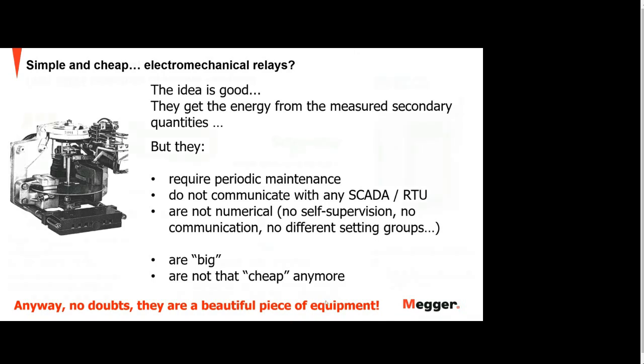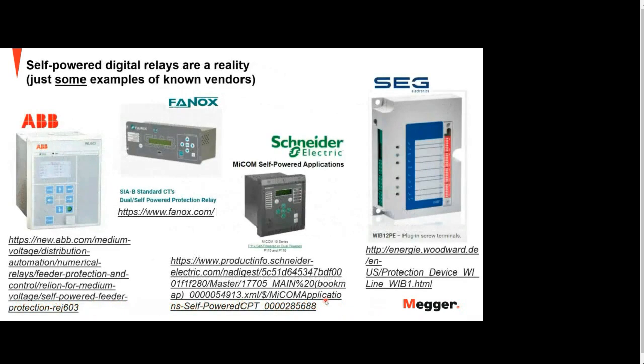So nowadays, we have the self-powered relays, digital relays. They are a reality. And here we can see some different manufacturers of self-powered relays. So self-powered relays are a test challenge, of course. The first thing is that you need to have power from the current generator when you test the self-powered relays.